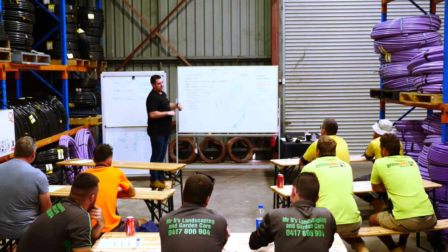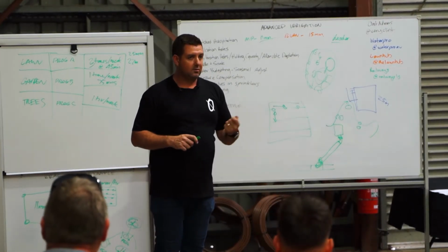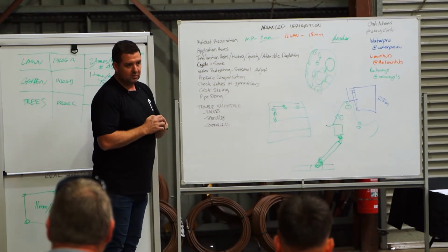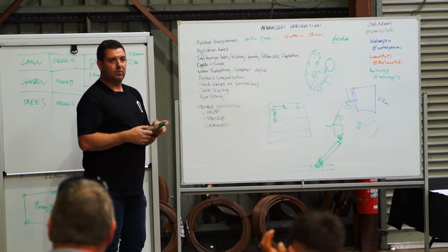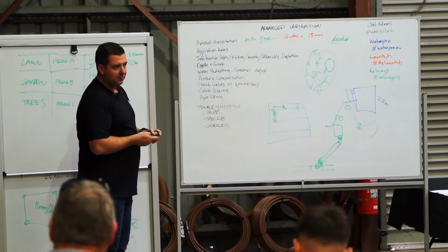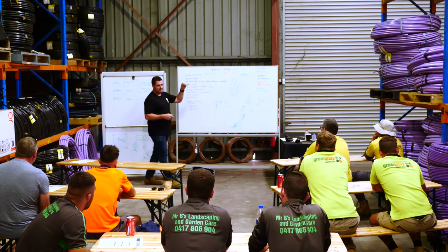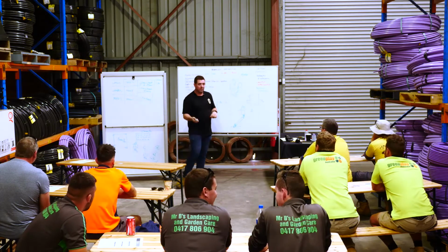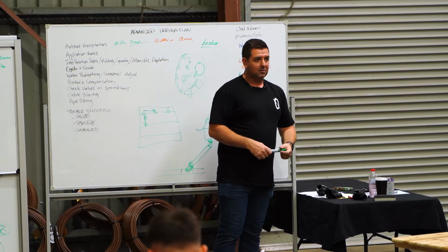If you don't have the right size cable, you're not going to deliver the right amount of electricity to the solenoid valve, and it's not going to work. It's that simple. We have commercial situations where the commercial contractor may have won the job at a super, super low price, and they're looking for savings. This is not somewhere you can save money. So you can't take 1.5 mil to 0.5 mil and hope for the best. You can't have 0.5 mil run for the first 100 meters and then join it to 1.5 mil and hope for the best, because the builder won't see it.